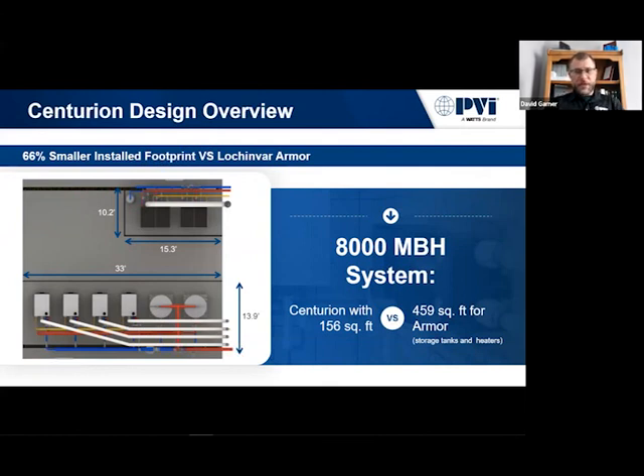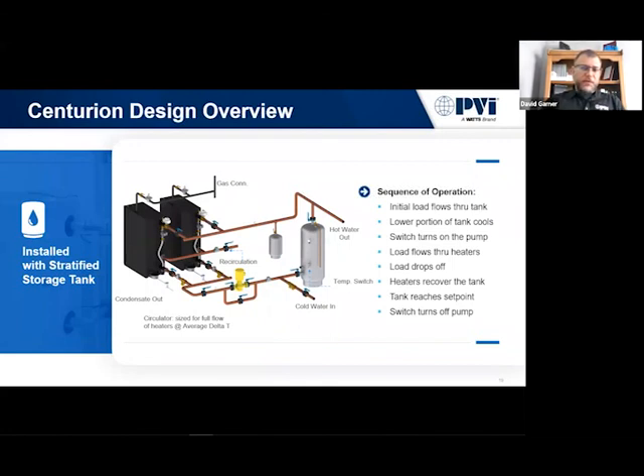The last thing I want to throw out here real quick is we also have the ability to pair these with a storage tank. This would be for a system that has a dump load. So I always think like hotels. If there's on-site laundry, you're going to need a storage tank because they're going to have that dump load. If there's a hotel that does their laundry offsite, we can just line these water heaters up. That's just a quick example, but we have the ability to size these for whatever's appropriate for that system.